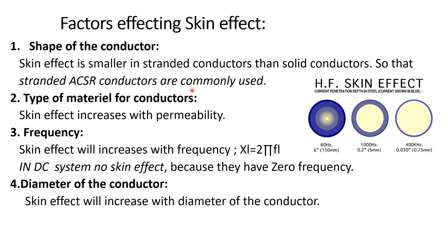Now let us discuss the major factors affecting skin effect. The first factor is the shape of the conductor. Skin effect is smaller in stranded conductors than solid conductors, which is why stranded ACSR conductors or bundled ACSR conductors are commonly used.